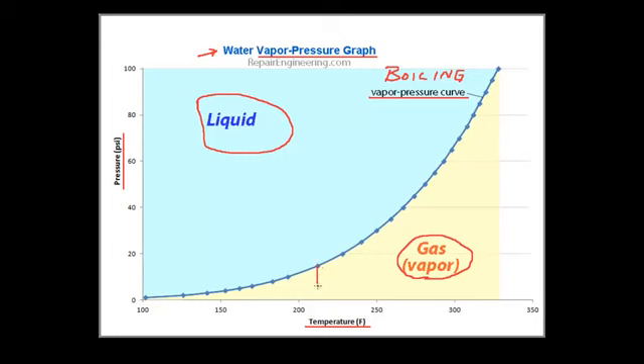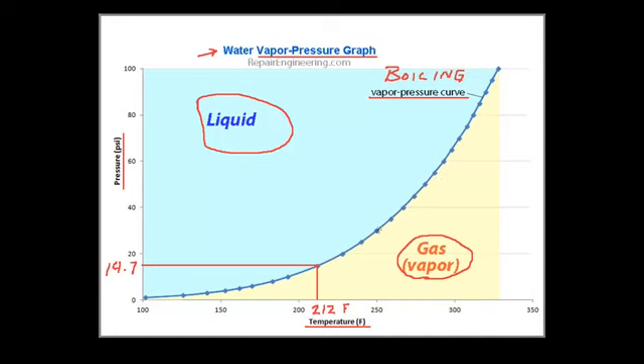To see how this graph works, let's use a couple of examples. Many people, when asked if they know the boiling temperature of water, will answer that it boils at 212 degrees Fahrenheit. This answer is partially correct. As shown by the graph, water does boil at 212 degrees Fahrenheit at the standard atmospheric pressure at sea level of 14.7 psi. However, notice that the boiling temperature of water changes with its pressure. In general, lower boiling temperatures correspond with lower pressures, and higher boiling temperatures correspond with higher pressures.